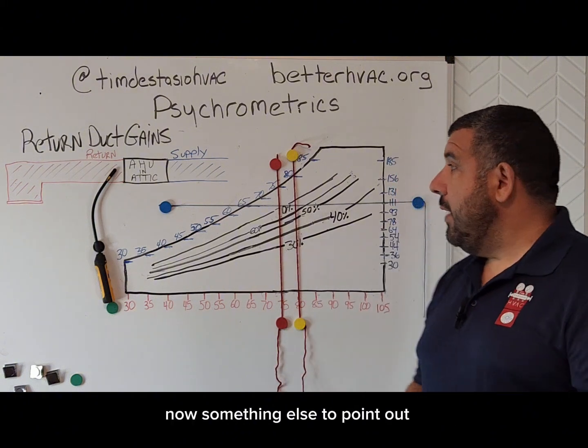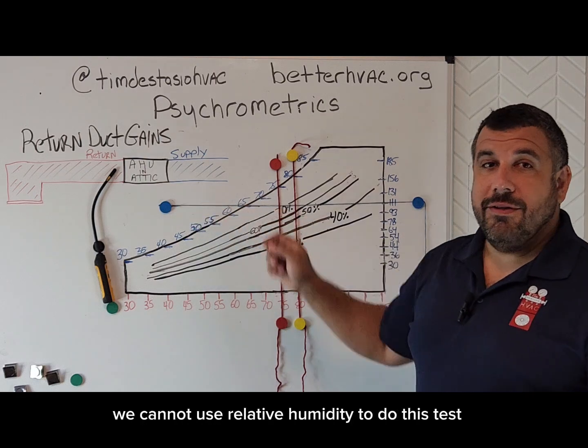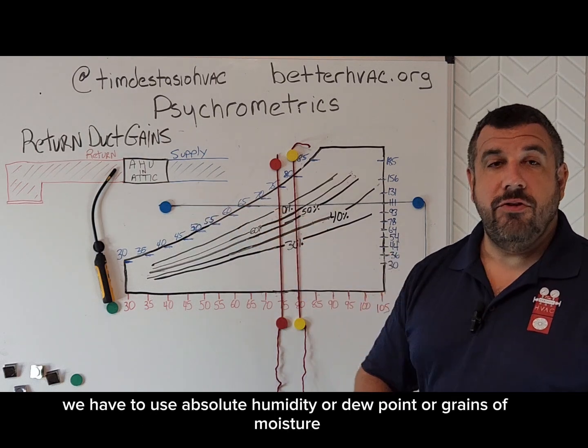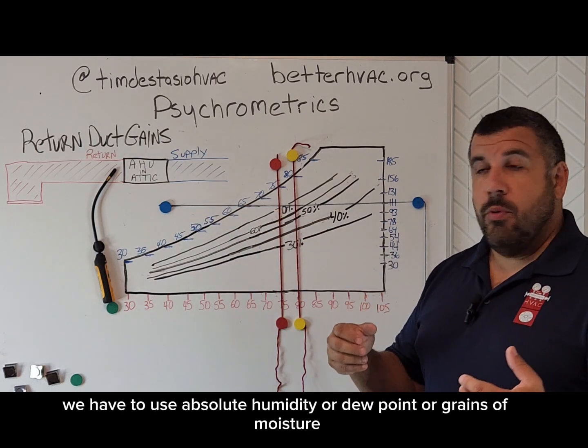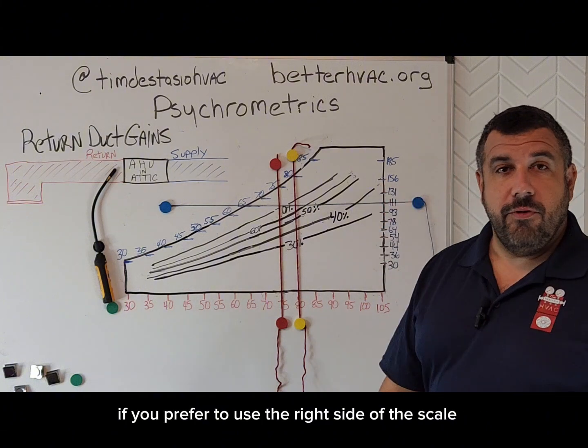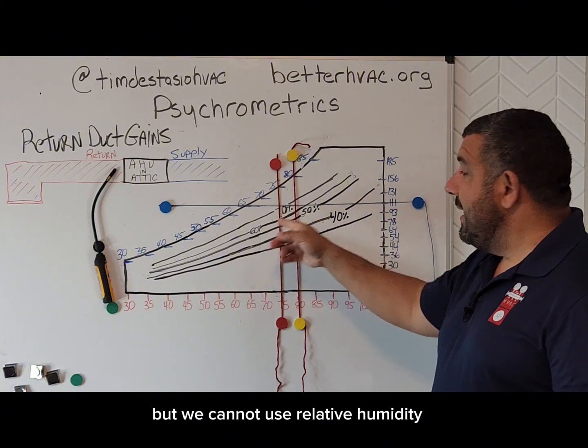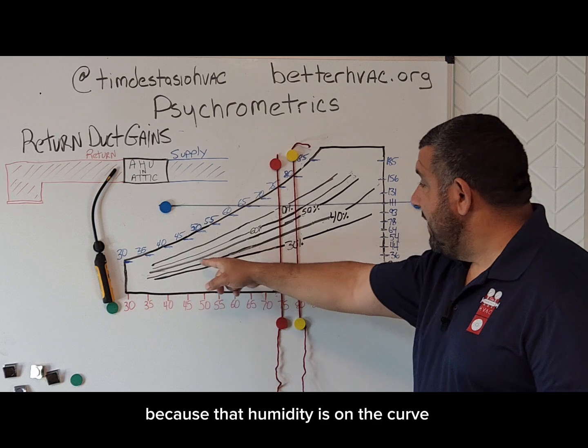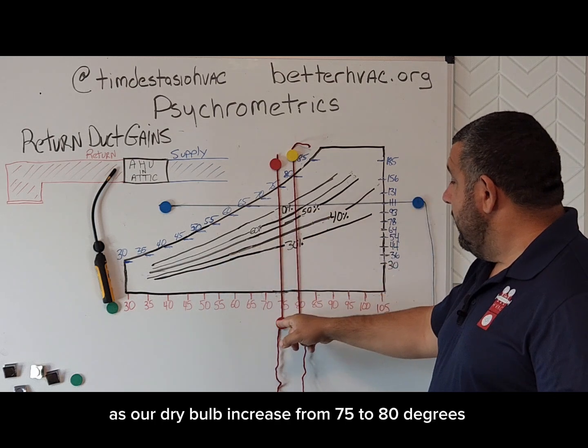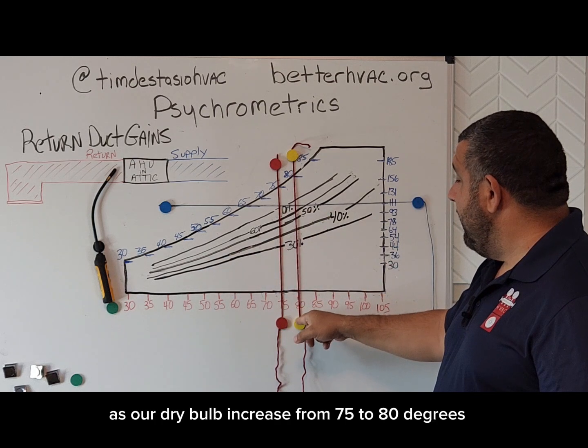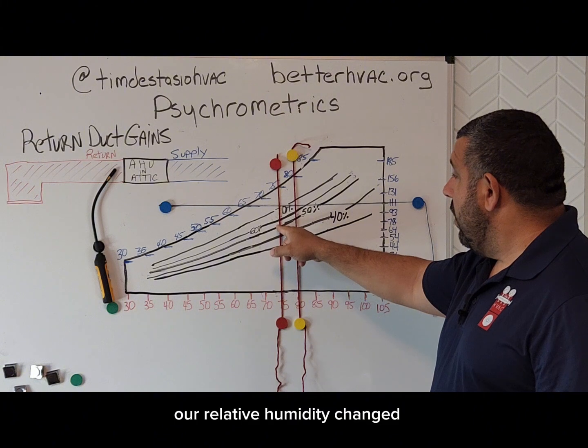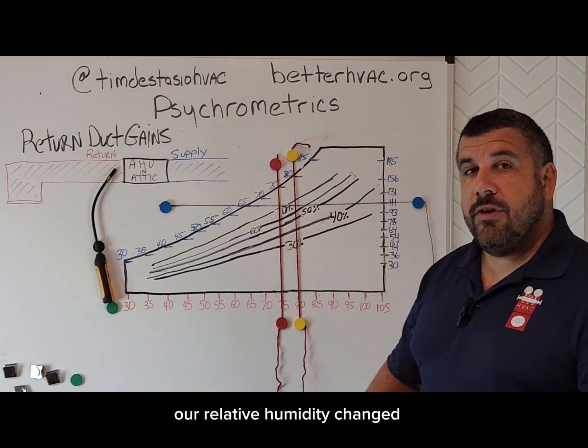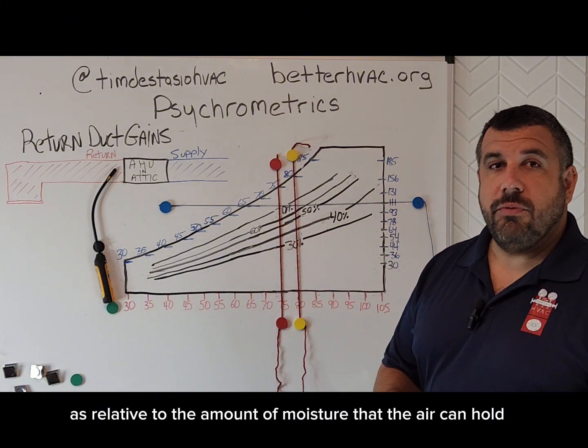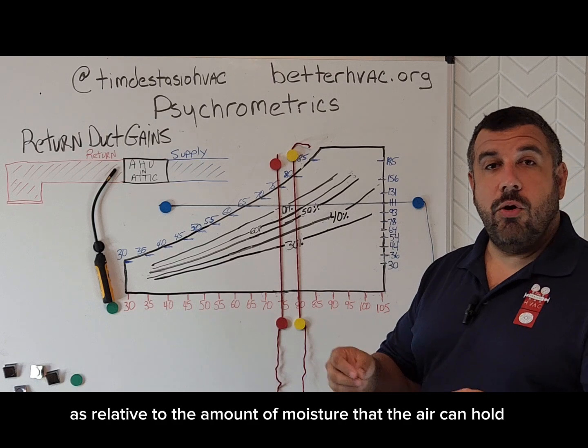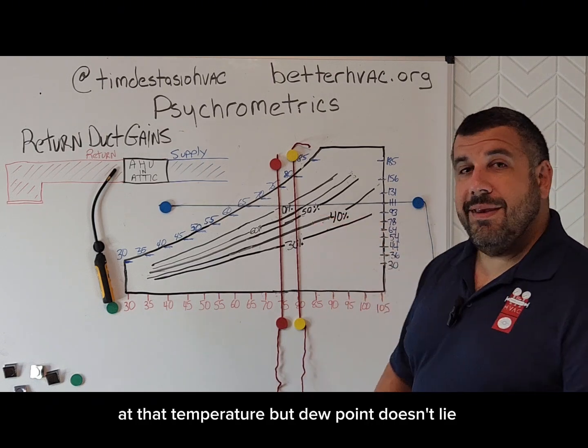Now, something else to point out, we cannot use relative humidity to do this test. We have to use absolute humidity or dew point or grains of moisture if you prefer to use the right side of the scale, but we cannot use relative humidity because that humidity is on a curve. As our dry bulb increased from 75 to 80 degrees, our relative humidity changed. And so relative humidity is just that. It's relative to the amount of moisture that the air can hold at that temperature, but dew point doesn't lie.